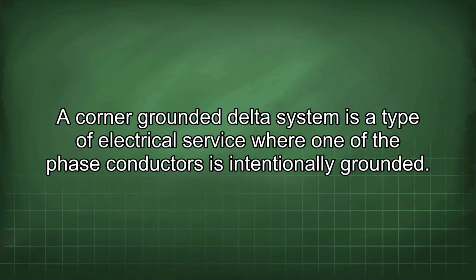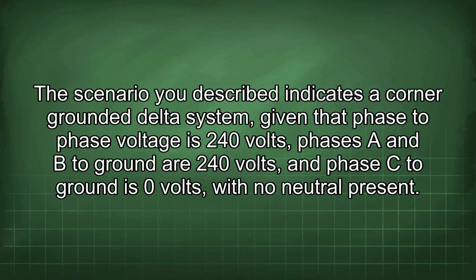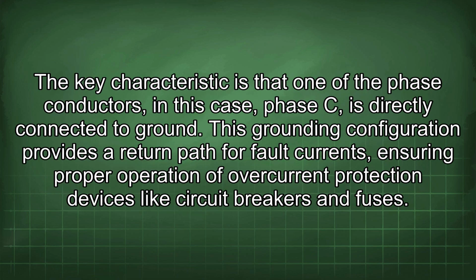Corner grounded delta system is a type of electrical service where one of the phase conductors is intentionally grounded. The scenario you described indicates a corner grounded delta system, given that phase-to-phase voltage is 240 volts, phases A and B to ground are 240 volts, and phase C to ground is 0 volts, with no neutral present. The key characteristic is that one of the phase conductors, in this case, phase C, is directly connected to ground.